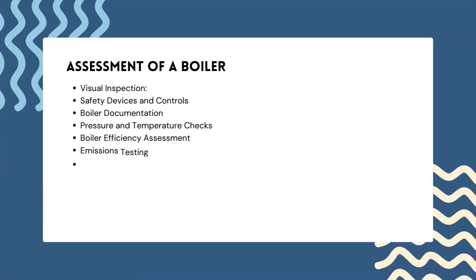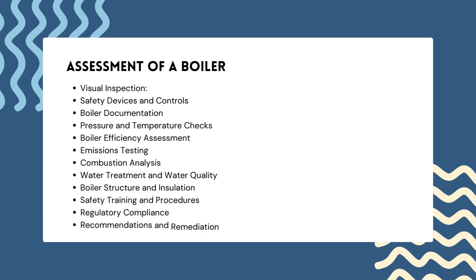The assessment of a boiler is a critical process evaluating its condition, performance, safety and compliance with regulations. Regular assessments are essential to ensure efficient and safe operation. Key steps include: first, visual inspection — beginning with a visual inspection of the entire boiler system including the boiler itself, associated equipment and safety devices. Look for signs of damage, corrosion, leaks and worn-out components, and check for proper labeling of critical components.